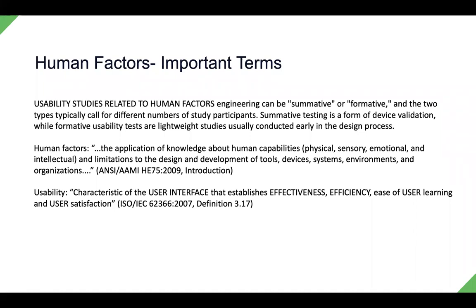The other aspect of usability studies is what's usually referred to as summative, which is sort of the sum total of your product. You're now entering into your verification and validation phases where you're pretty sure that you're done and have got what you need. And it's a much more heavyweight process, and you hopefully have done your homework through the formative studies so that you don't find issues there.